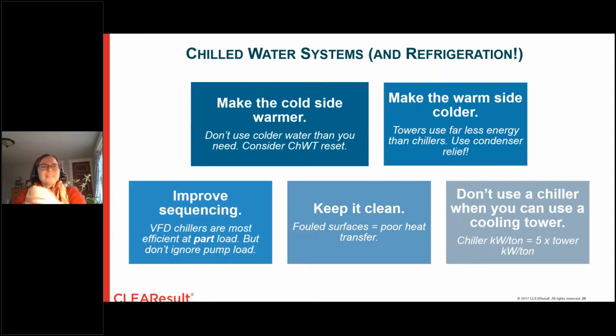Keep it clean. I see a lot of filthy cooling towers, and that means really bad water distribution and really bad heat rejection. You're not going to get as cold of water out of a filthy tower as you are out of a nice clean tower. And you're probably gunking up your condenser on your chiller too, which means a hotter hot side on your chiller, which is poor lift, poor power.